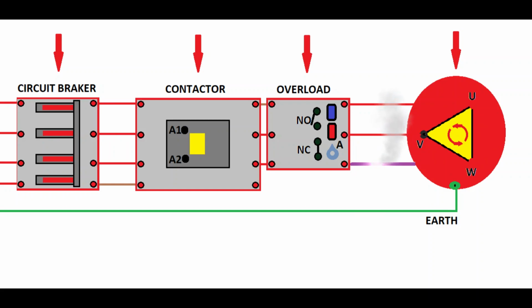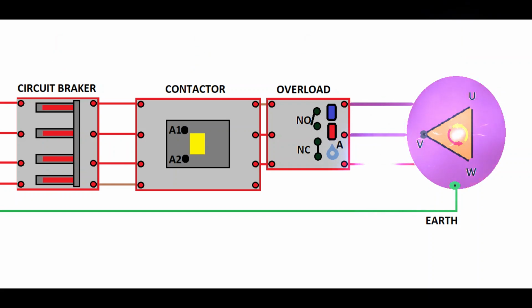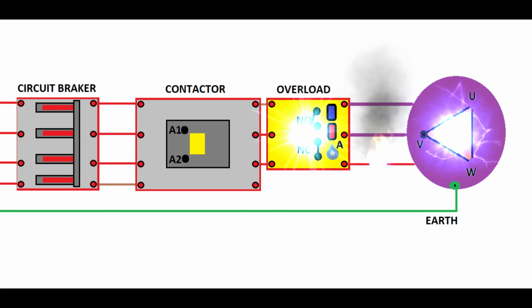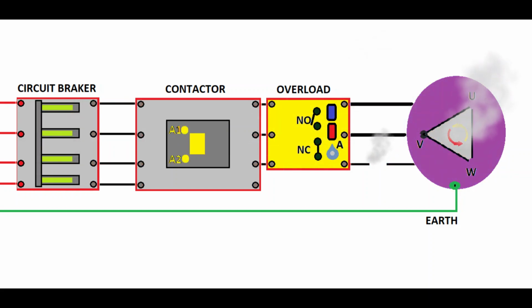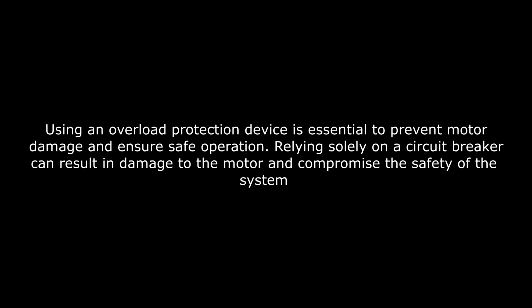So just look at this, what can happen if you do not set an overload correctly. The motor will run, one cable might burn, the other two will increase the amps. The overload will try to heat up, but it is set up too high, and finally the circuit breaker will trip, but your motor will be damaged. So if you use an overload protection, it is essential to set the overload correctly.